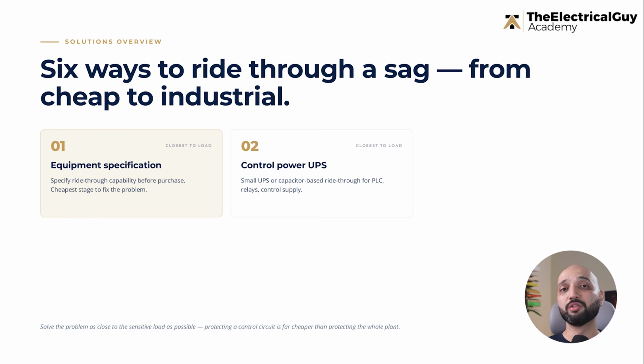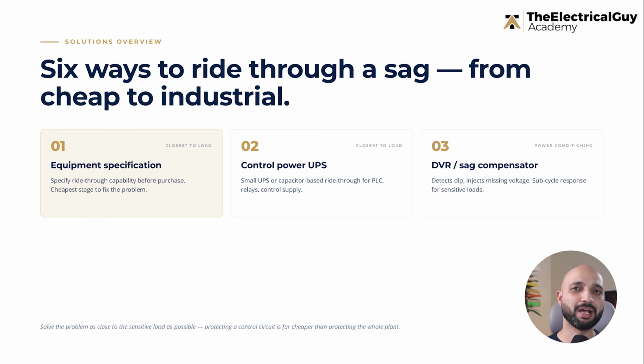The third solution is using a voltage sag compensator or dynamic voltage restorer. These devices detect voltage sag and inject the missing voltage so that the load-side voltage remains within an acceptable range. For example, if the supply voltage dropped to 40%, the compensator injects the required voltage to maintain the load voltage. Some devices operate very fast, within a fraction of a cycle. These are useful for sensitive industrial loads where downtime cost is very high.